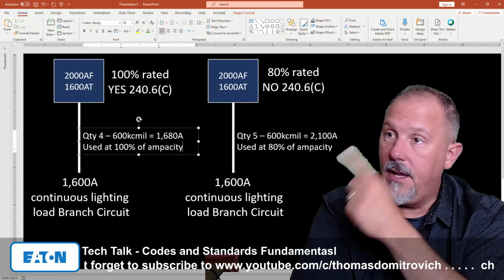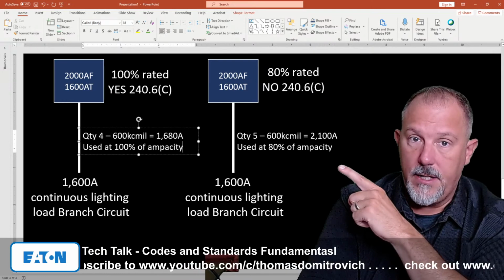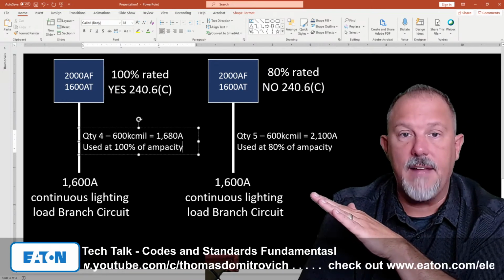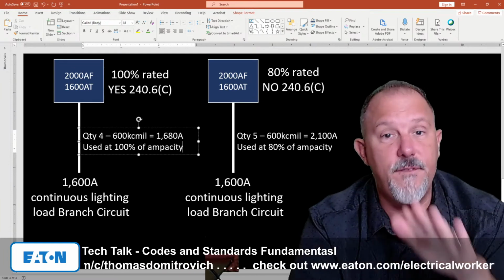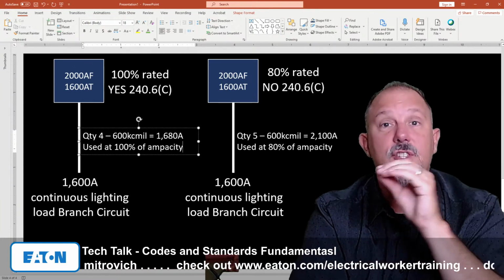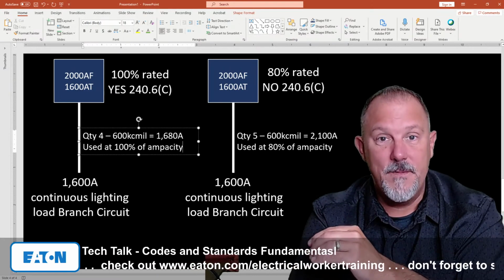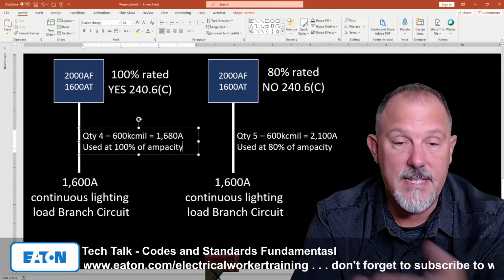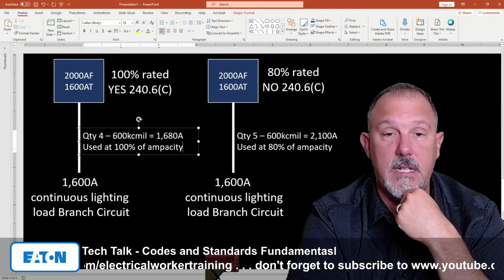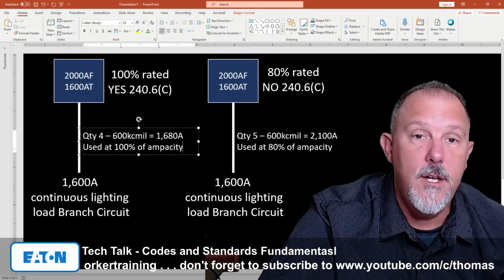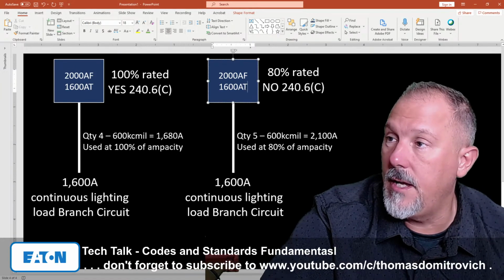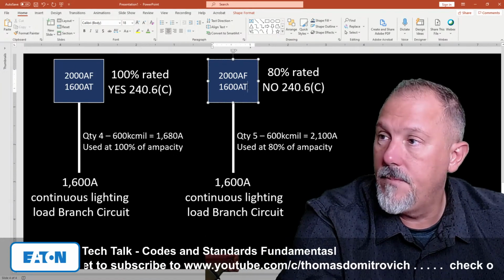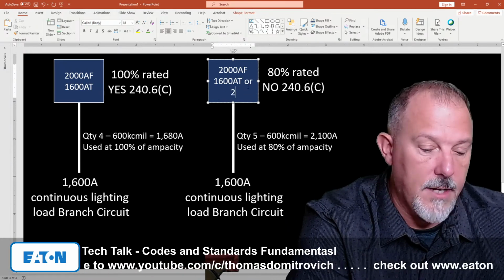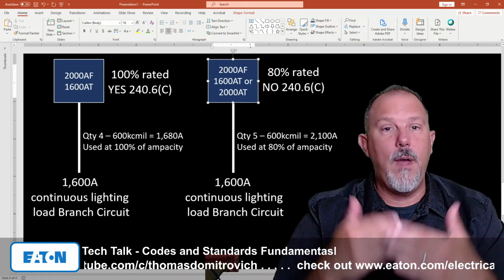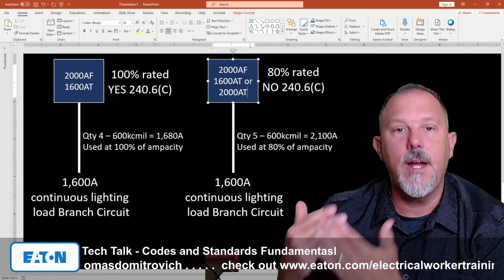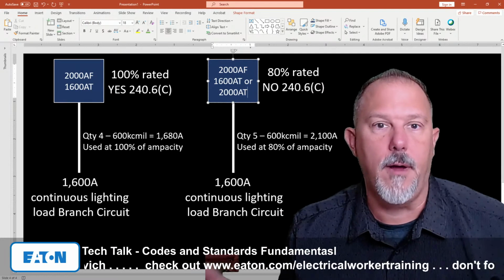On the other one, the 2000, the second one that I don't have the 240.6c, I've got to have 2000 amps worth of conductor. That's why I have 5 600 kcmils, and they can serve 80% of the 2000 amps, which is 1600 amps. I could set that breaker to trip at 1600 amps, but I don't have to. I could take this circuit breaker and say, look, we'll do a 2000 amp trip, because either way, I'm protecting 2000 amps worth of conductor at 2000 amps. I just happen to have 1600 amps worth of load on it.